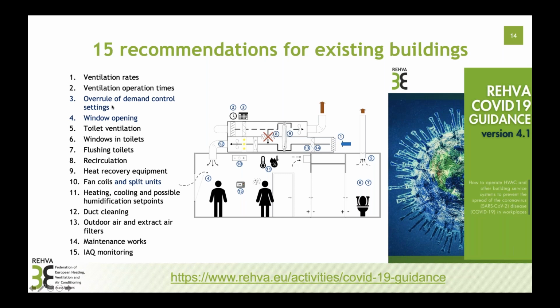When indeed, if a ventilation is demand controlled, this is not a good feature for the epidemic where you need a maximum amount of fresh air, when this will need to be overruled, when there are a set of recommendations, if there are natural ventilation systems, what to do, and also dealing with ventilation hygiene, like heat recovery equipment, recirculation, partly hygiene question, fan coils, split units, and some questions which are not so directly linked to that virus but have caused the confusion.